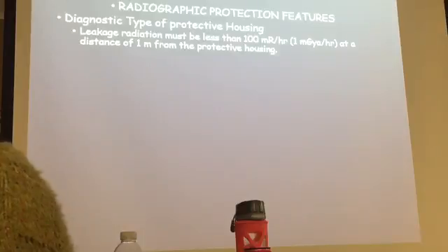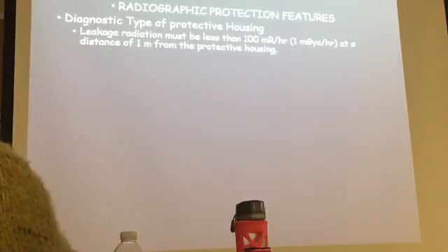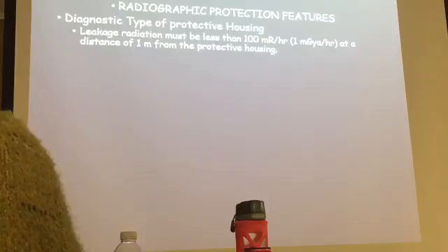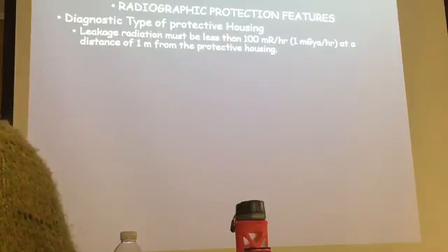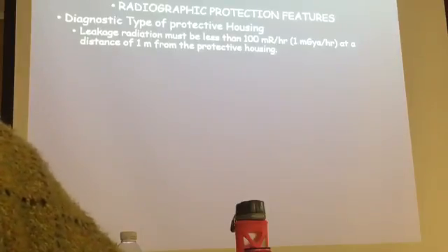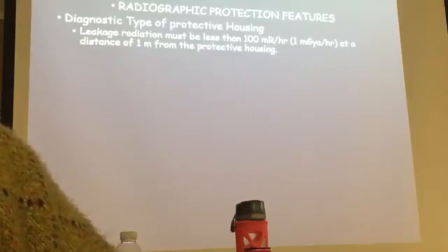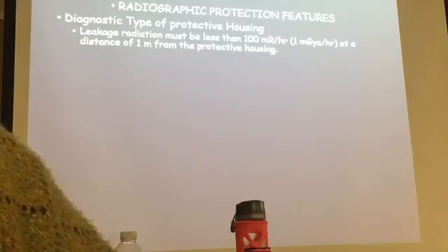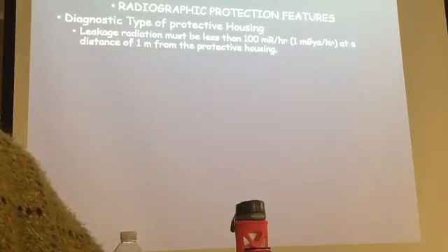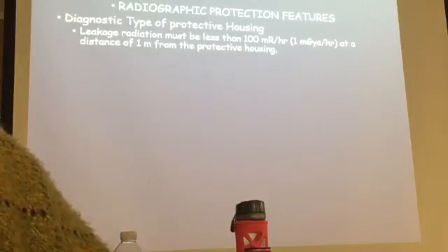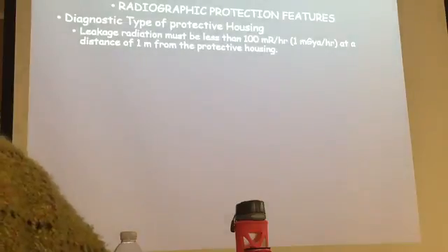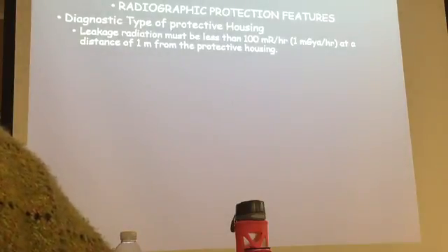Typically, you're going to go to the highest settings you have, highest mA and highest kVp. So you want to bring it to the top, the maximum amount of X-rays that you can create, and with the maximum amount of energy, and then you test it. But from what I've seen, they don't even come close to that. Might come to 50 milligray. Very, very low.